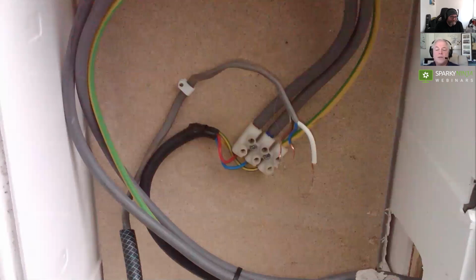But does it not depend on what it's supplying? Completely. If it's a circuit that requires RCD protection and it doesn't meet standard, we'd be looking at a C2. If it's a circuit that doesn't require RCD protection but you put one in anyway, then arguably, as long as the overcurrent protection works, it might go down as a C3.